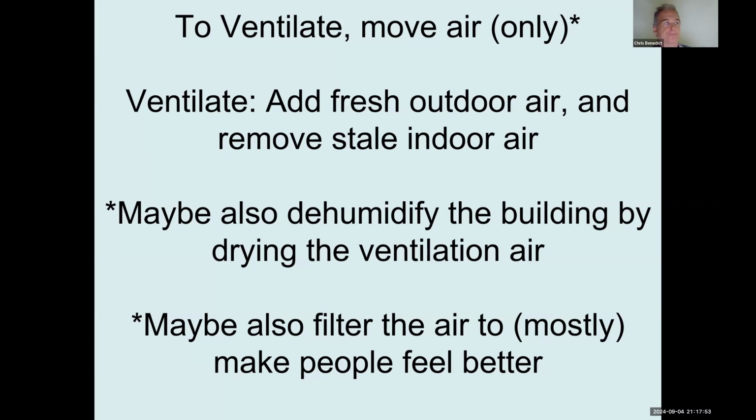And in the mid-Atlantic region, especially toward the Carolinas, this is more and more of a concern. There are many reasons why buildings are becoming more vulnerable to mold each year. And so dehumidification matters: the newer the building, the more vulnerable the materials are to mold. Wood, mold can eat it, but it prefers plywood and it much prefers OSB and even more likes paper-faced gypsum board. A plaster wall will kill the mold. Plaster is a pH of 14. You're not going to see mold on a plaster wall in significant quantities.